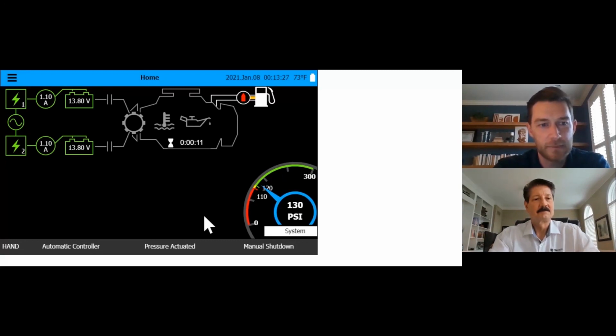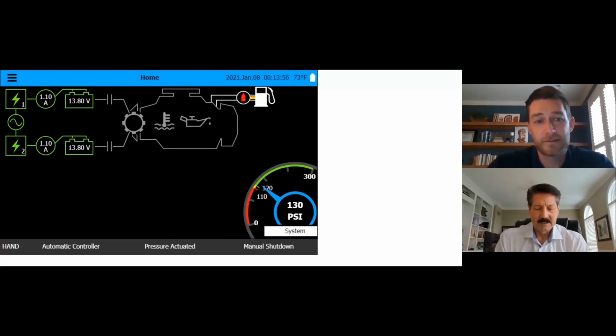So you can see on the top left, we're going to have the two chargers. That's the two lightning bolts there. That's signifying that we have power coming in. Everything is good. To the chargers, they're sending a 1.1 amp trickle charge to the batteries. So we've got two different modes for the battery chargers, either a bulk or a trickle charge, like a float. Floating, the trickle charge, is where you want it to stay the majority of the time. If it's going to be a bulk charge, it's going to be burning out the charger.